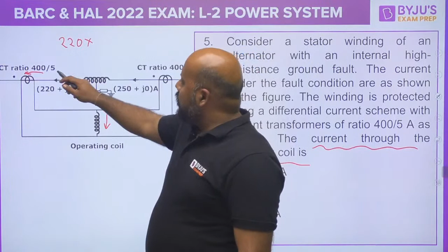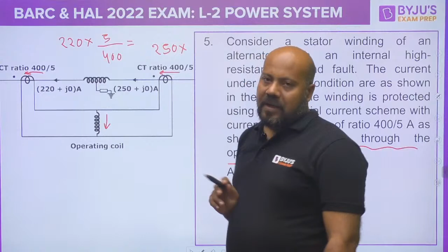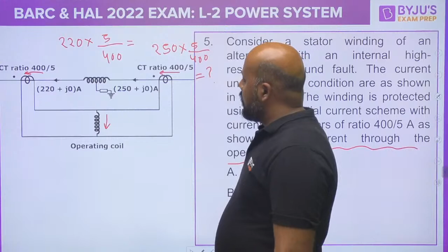Now you tell me why you are using the current transformer, why you are not directly taking the sample of the current. Please try to understand. One thing is, directly you cannot take the sample. Also, when we are using the current transformer, our intention is we don't want to directly deal with the fault current, we want to deal with a lesser current. It means the current reflected in the secondary of the CT, where the primary of the CT is the line itself, is going to be a lesser value. How can it be a lesser value?